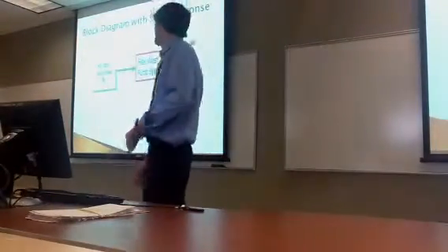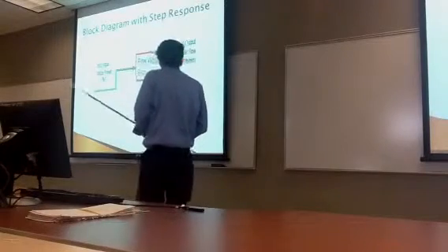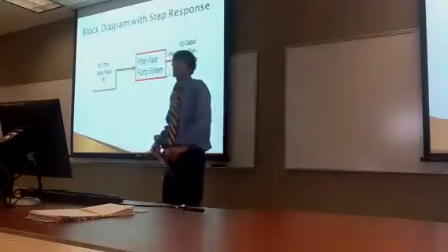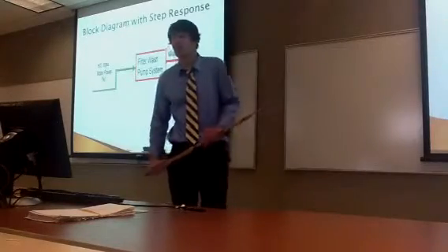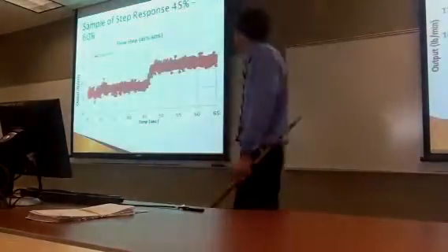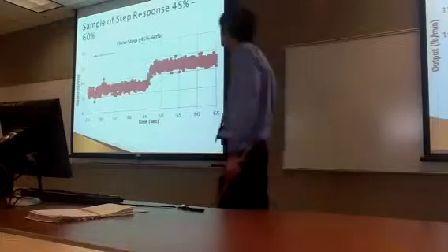Now this shows the step response, in which the input power is going to either step up or decrease. In our tests we did 15% increases and decreases. This is an example of one of our step responses, stepping from 45 to 60.